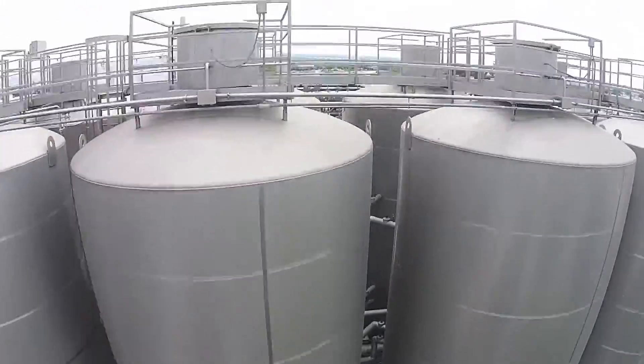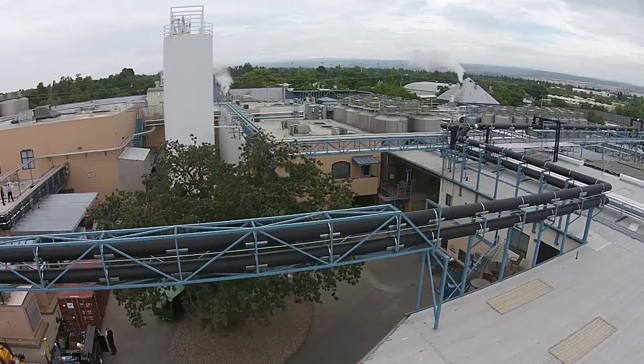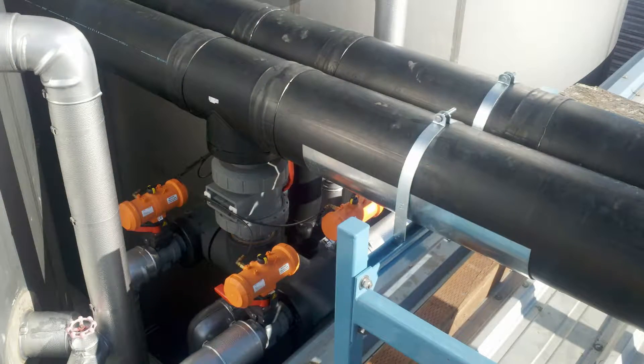I'm thinking smaller diameters — two or three inch — and I thought what was interesting about this installation is that you've got some relatively large pipe for glycol. How big a pipe are you using here? You're absolutely right. Breweries by nature take a lot of process cooling. Being that we installed a central plant — just one location, piped from that to all of our fermentation cellars — we started off with a 16-inch diameter electrofusion piping, ran a couple hundred feet of it, then broke it down to 12-inch diameters, which is socket welded with glue, down to 10 in some areas. Most of our headers are in the 10-inch diameter, then reduced to some sixes and some fours, and then down to our points of use — twos and such.